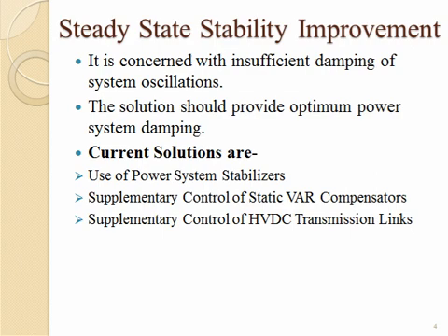Now another technique is supplementary control of static VAR compensators. Why does the word supplementary come over here? Because the ultimate role of a static VAR compensator is reactive power compensation. But at the same time, if you can have some adjustment in their control actions, they can simultaneously help in damping oscillations in the system.